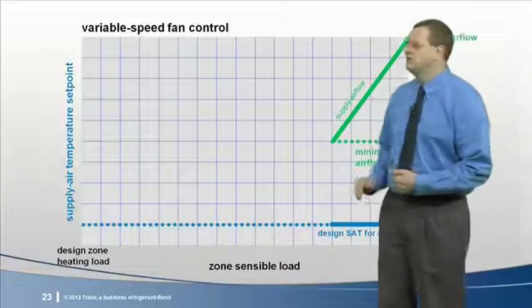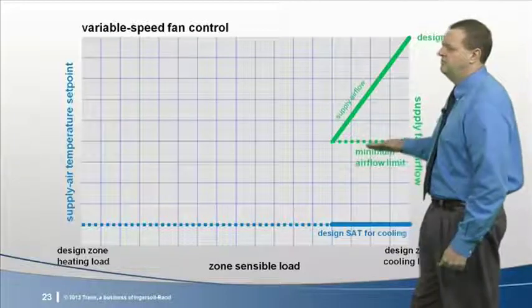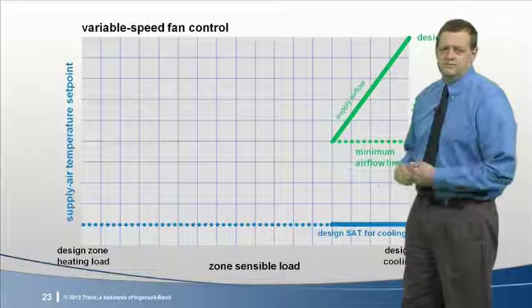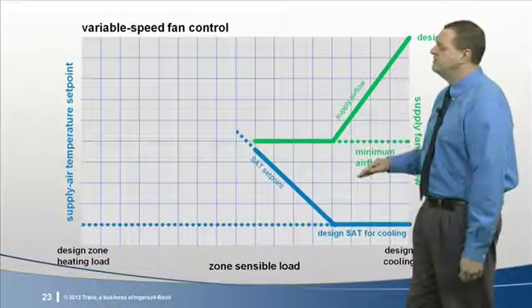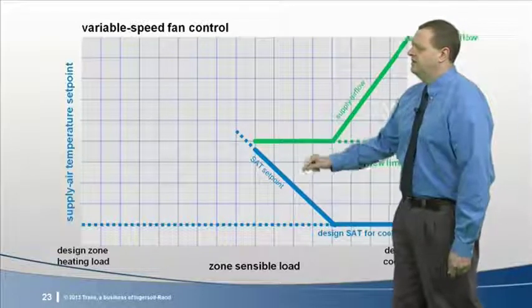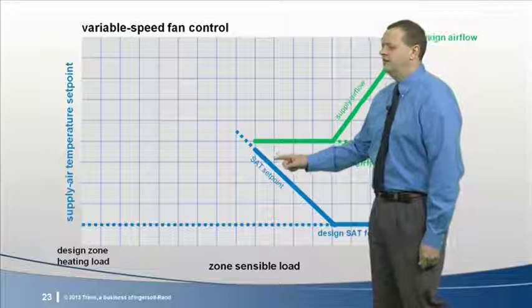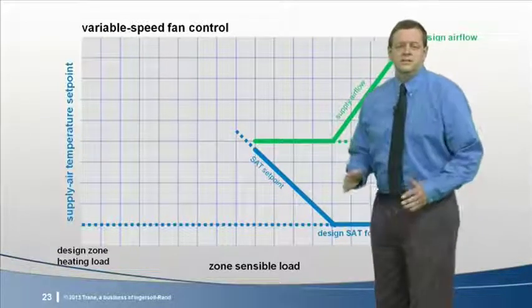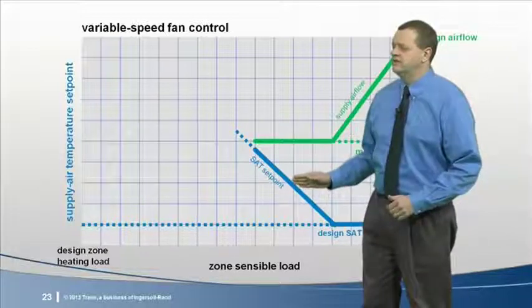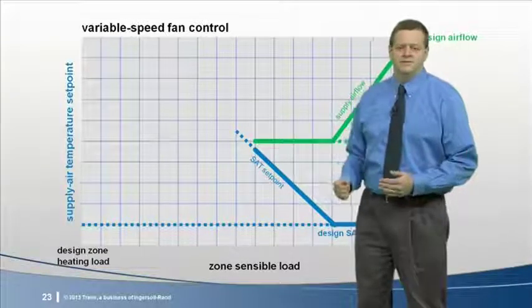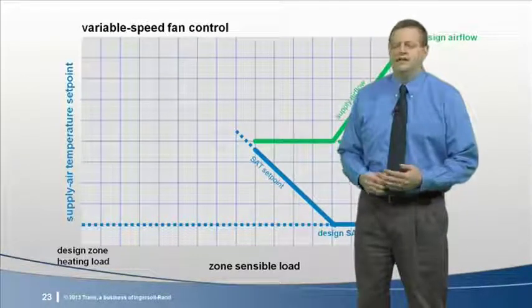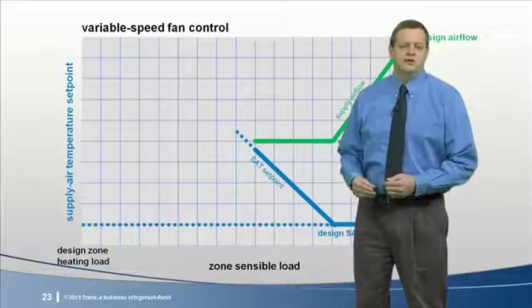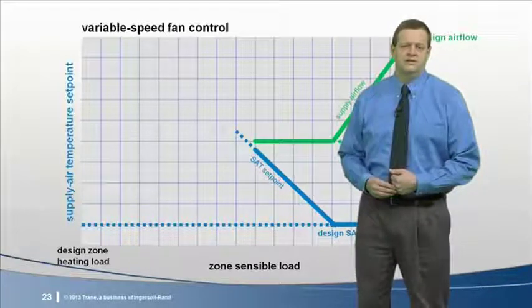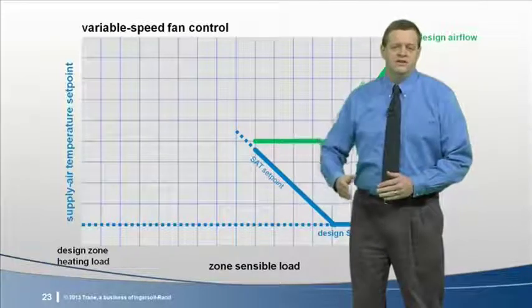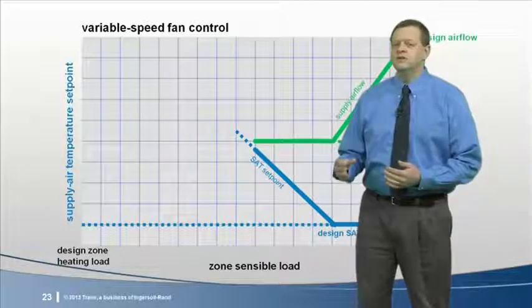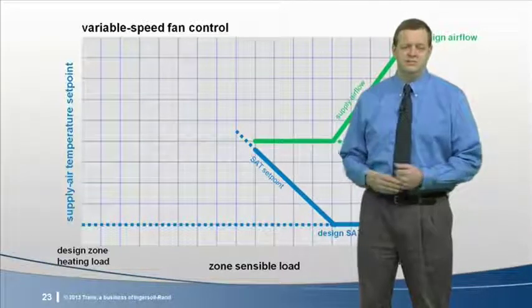Now eventually the zone cooling load decreases to the point where supply airflow reaches some minimum limit. I'll come back to discuss this limit a little bit later. As the zone cooling load continues to decrease, the fan continues to operate at this minimum airflow. But now the supply temperature set point is gradually reset upward to avoid overcooling the zone. Depending on the outdoor conditions, as this temperature set point increases, eventually no mechanical cooling is needed to make this temperature, so the compressors are turned off. And even the airside economizer modulates back to bring in only the minimum outdoor airflow required for ventilation. When that happens and the load continues to decrease, the zone temperature begins to drop below the zone's cooling set point into the dead band between cooling and heating set points.